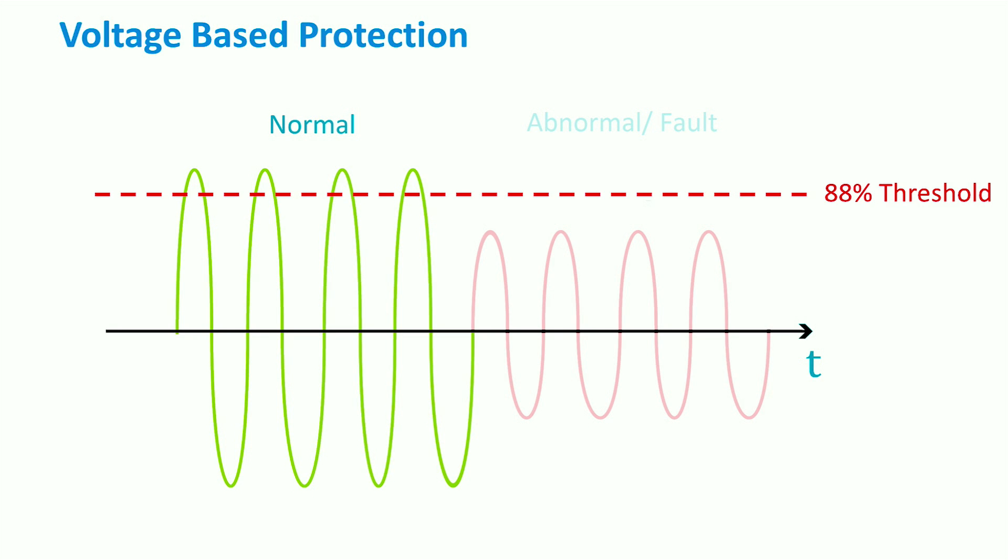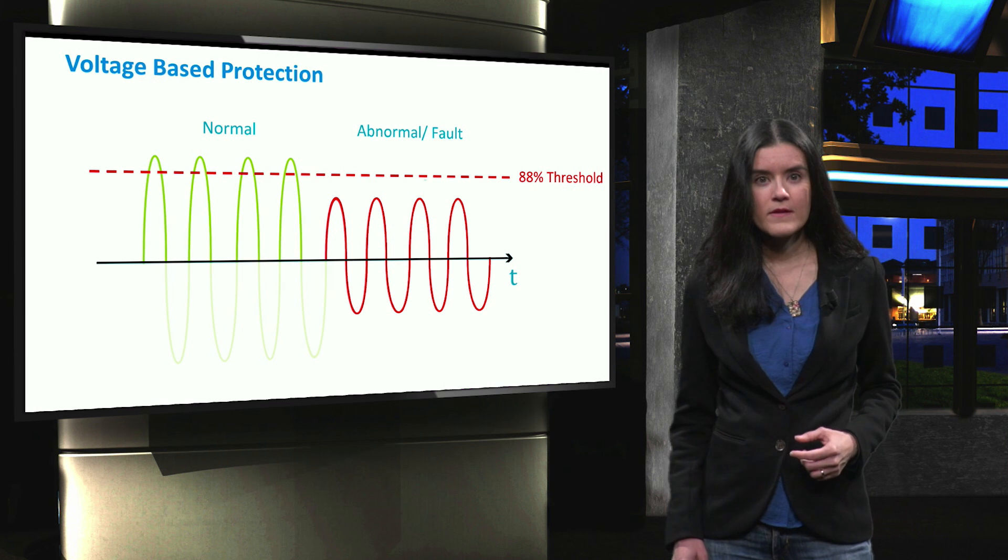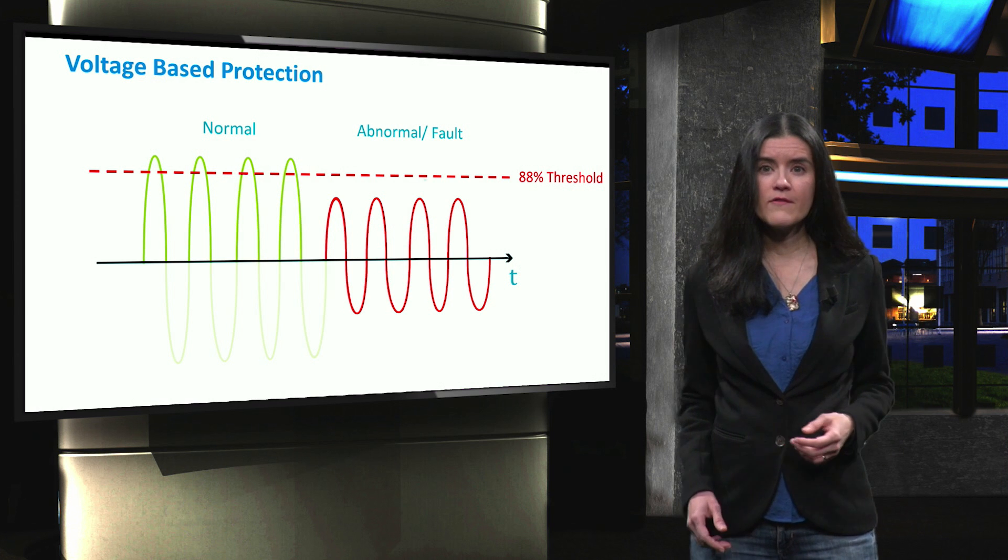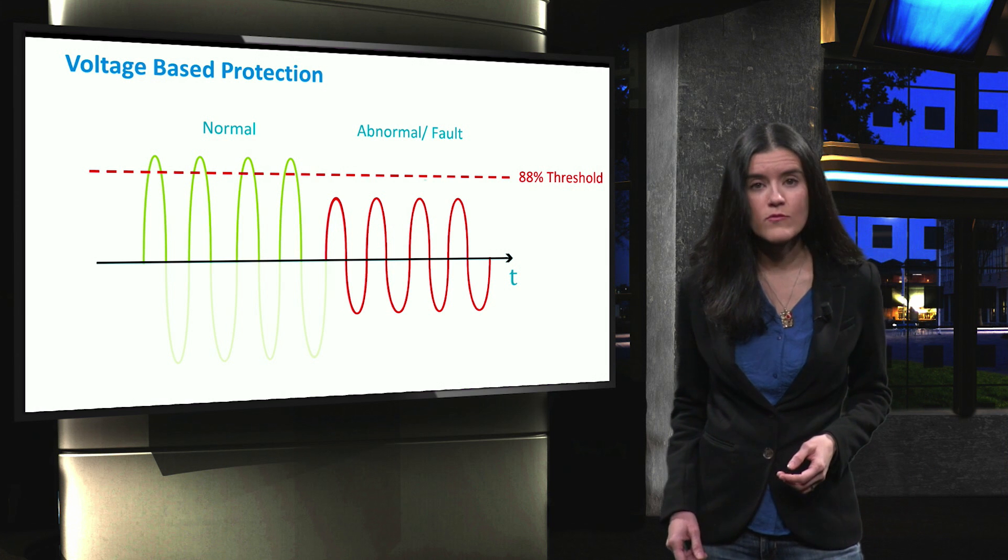If the value falls below 88%, this is seen as a fault close to the distributed generator. This leads to the intervention of the control system to limit the output current of the distributed generator. The main advantage of these methods is that they are unaffected by the current value or direction in the network.